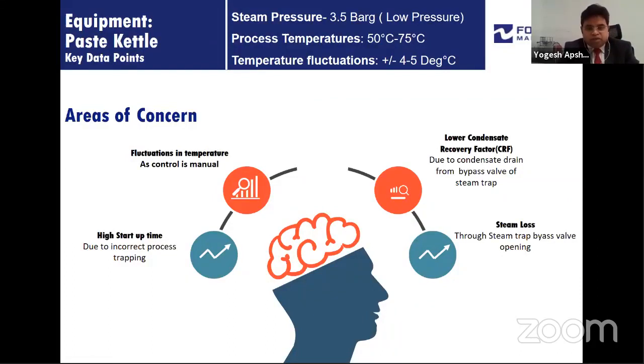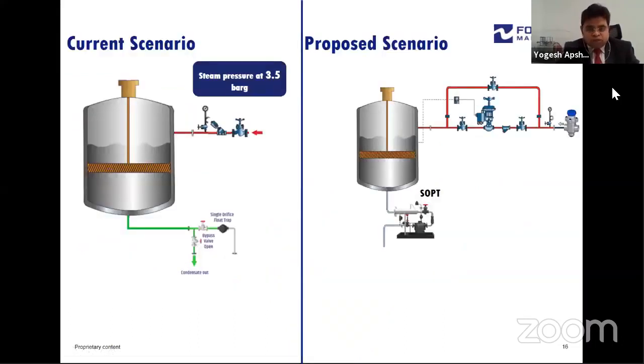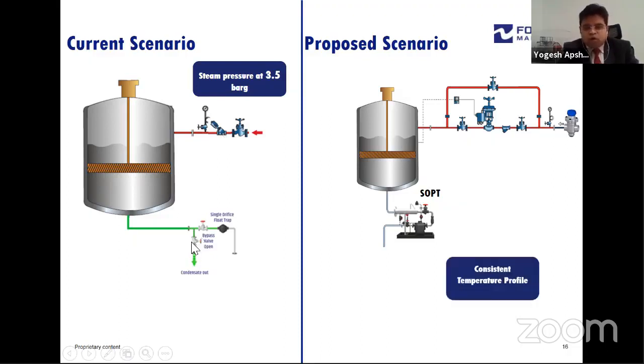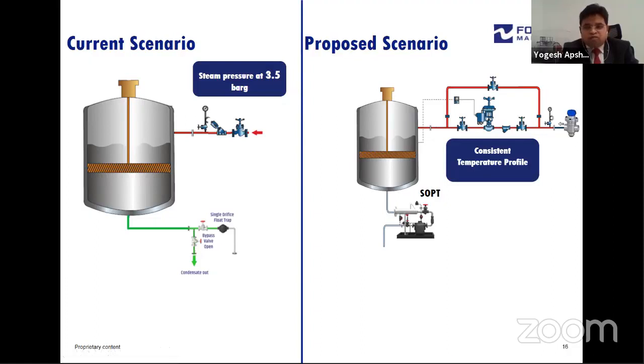Going on to the next equipment, which is a paste kettle. Most of the places we have seen have higher startup time, then fluctuation in the temperature as the control is manual, then lower condensate recovery factors, and steam losses due to the steam trap opening. So these are the typical issues, areas of concern we have seen. On the left hand side you will see a typical paste kettle with only an isolation on-off valve, and a steam trap with the bypass valve open. So how do we make it more efficient?